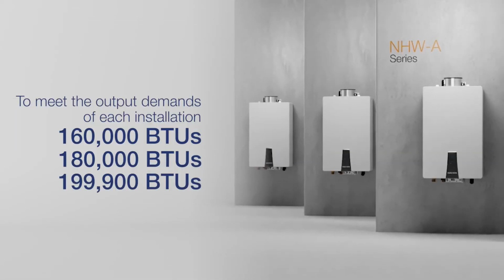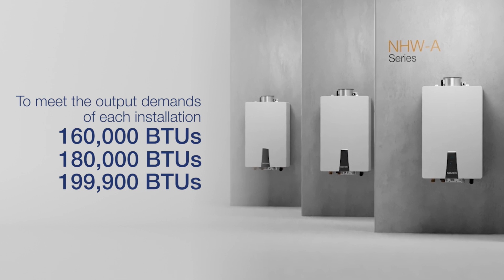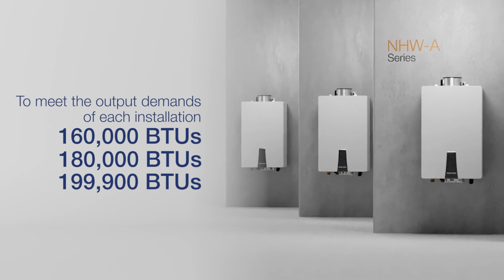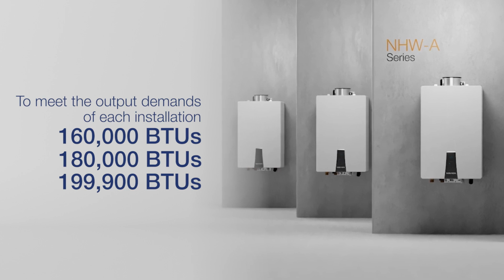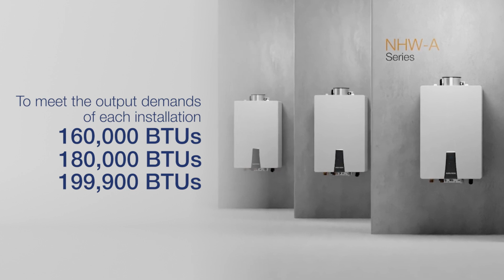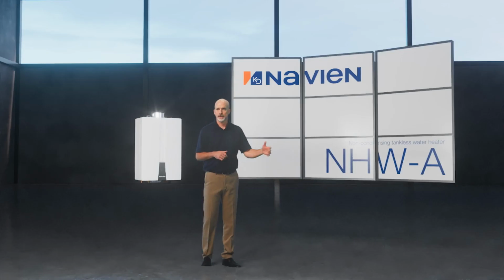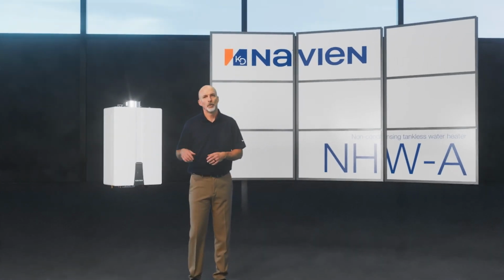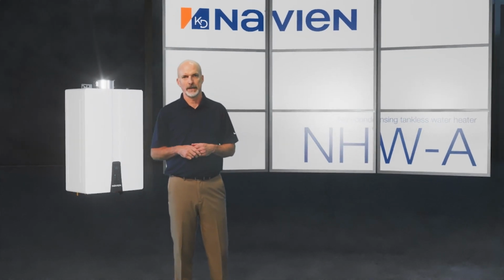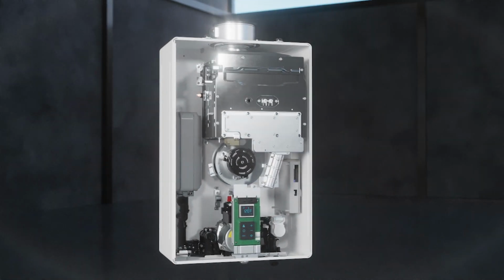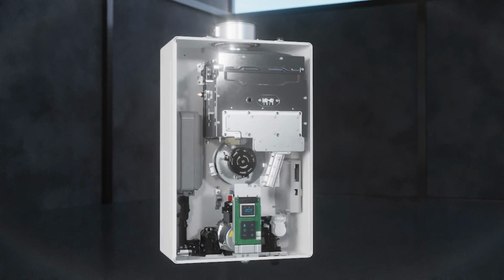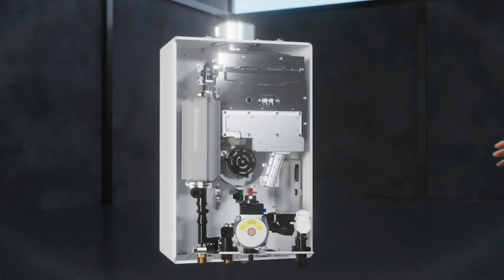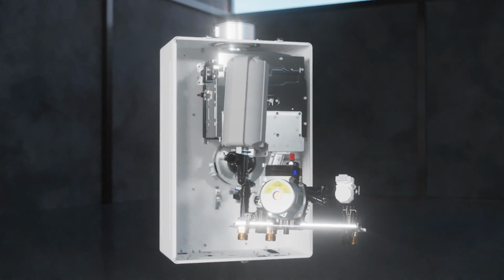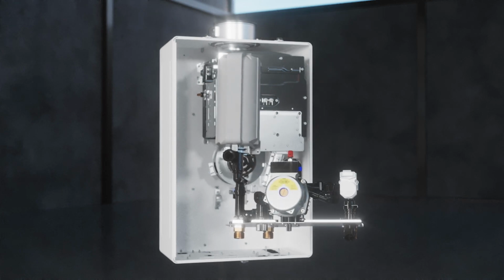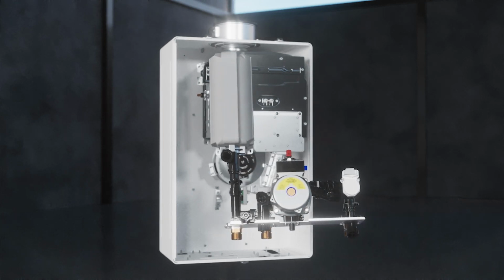Contractors have the option of three sizes, a 160, a 180, or 199,000 BTUs, to meet the total flow demands of each installation, all available in the same compact cabinet. All of these features of the NHW are great, but what matters the most is what's inside the box. Here are a few of the proven components of the all-new NHWA that set it apart from other non-condensing tankless. The patented Navien Comfort Flow Recirculation System achieves a few major benefits. It helps eliminate that cold water sandwich that you get with other systems.